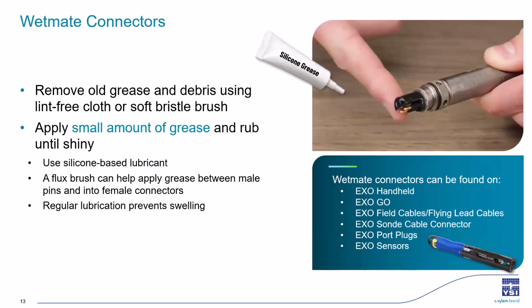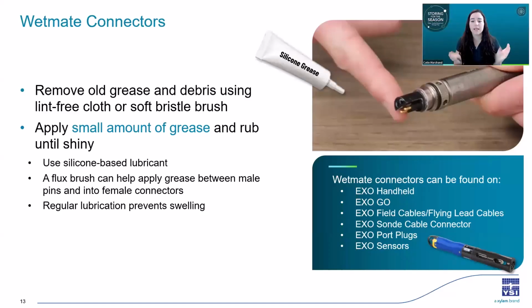And this also goes for the cable connectors as well, on your cable and on the top of your instrument. So to take care of them, take the sensors and port plugs out. Use a lint-free cloth or soft brush to clean off old grease and dirt. Then apply a little pea-size amount, again, of silicone grease. Rub it on the black neoprene just enough to make it shiny, and you're going to get both the male and the female connectors on these.